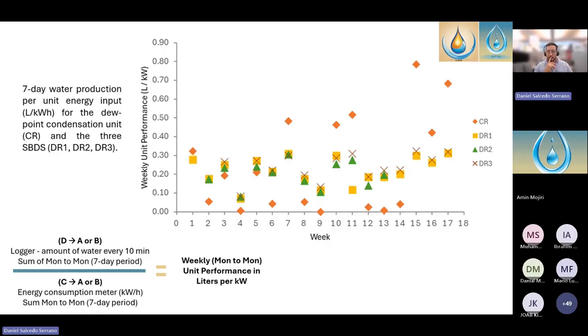So what we did also, with the amount of water that was being produced every 7 days and the amount of energy that was being consumed every 7 days, is a graphic where we try to see the unit's performance in liters per kilowatt. As you can see, the compressor-based, dew point condensation unit didn't do well for the longest time. It was really expensive to keep it running, and the production was really low up until the end.